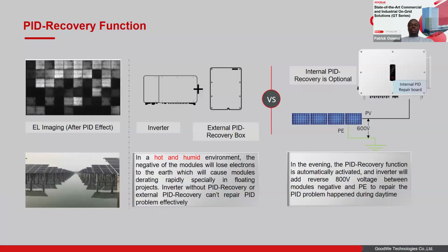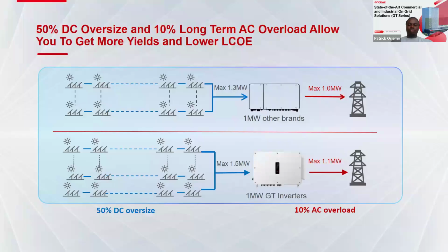Another optional feature, which you've seen from the coastal region or even the islands, hot, humid and saline conditions, we have the optional potential induced degradation feature, PID recovery. In this sense, if your panels are degrading because of the hot and humid weather, then at night the inverter will be charging the strings from the negative side up to 600 volts to restore the generation capacity of the panels. Come the next day, your panels will be generating to maximum, restored to their peak generation capacity. That is the PID recovery function.